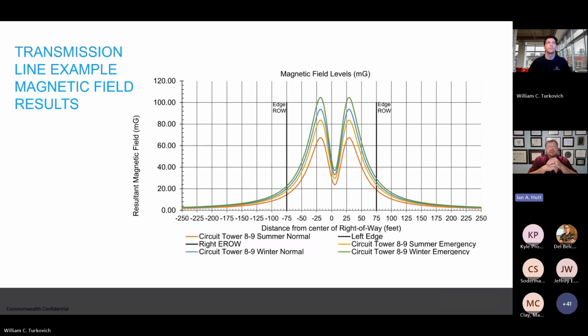We can see that in this particular scenario, that winter emergency rating is our peak. And it's giving us very severe magnetic field levels because we can put more current on that line. The ambient temperatures are cooler, so your sag and your conductor temperatures are going to be a little bit less. So your sag limits won't be exceeded here. But because those loadings and that current level is up, we're seeing that the magnetic field level corresponds accordingly and also goes up. It's a nice example to show that the loading level is directly proportional to the magnetic field peaks.